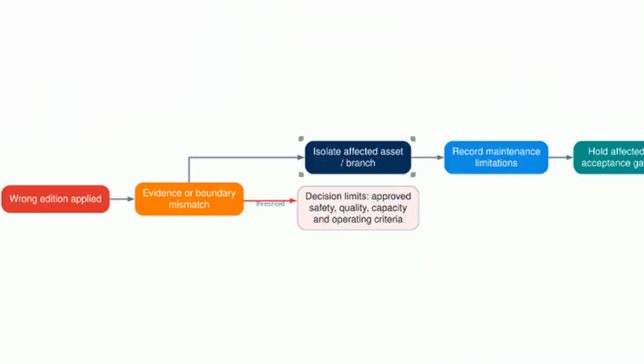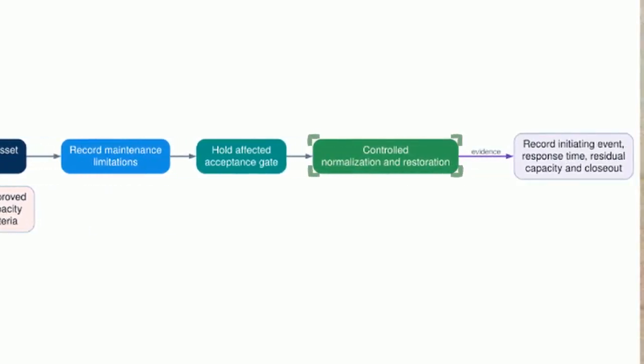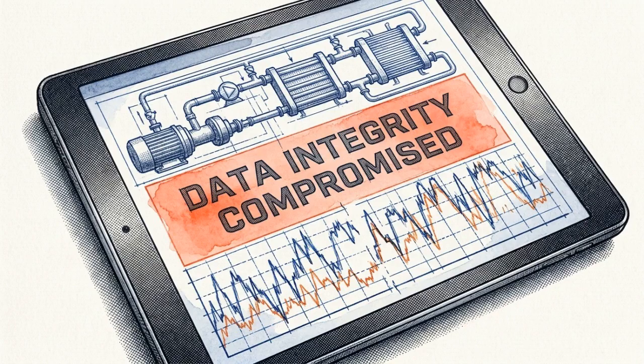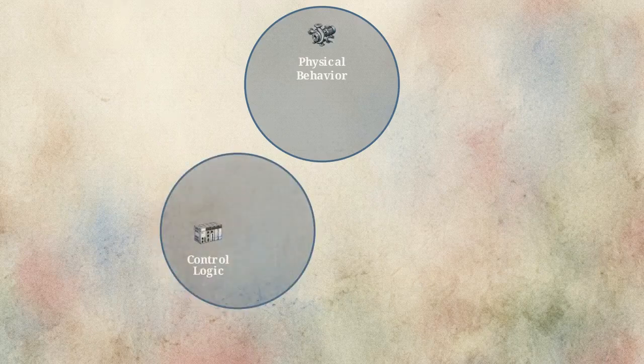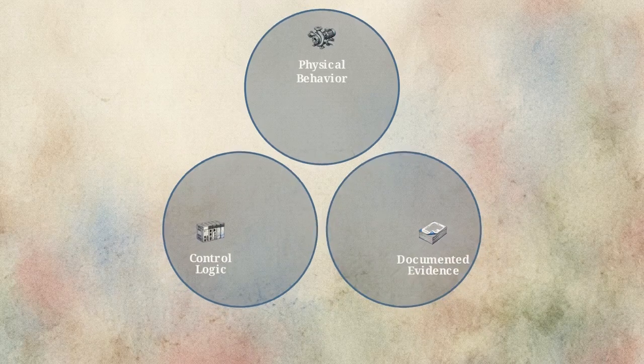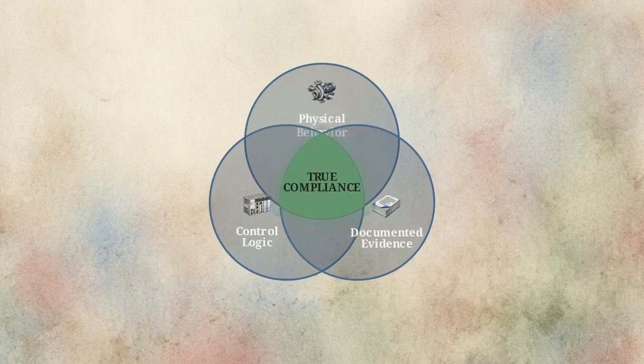This flowchart maps the discrepancy workflow. When the digital thread breaks, first isolate the asset and freeze data trends to preserve the as-found state. Once stabilized, verify calibration, authorize a management of change order, and execute a retest to establish a new baseline. Reacting to a mechanical anomaly without first freezing the data logs permanently corrupts the site's compliance baseline. True operational compliance is an active, continuous, and uncompromising alignment between physical behavior, control logic, and documented evidence.